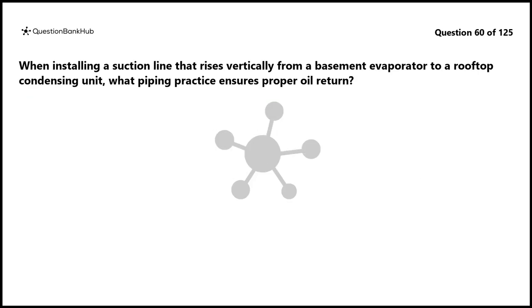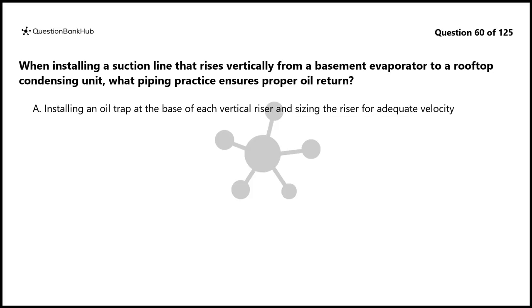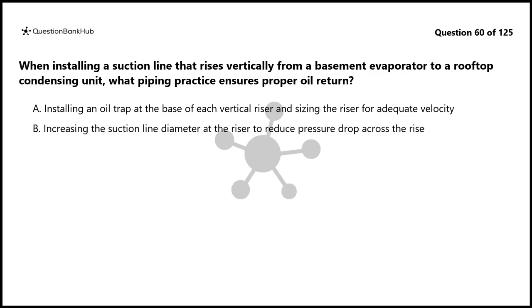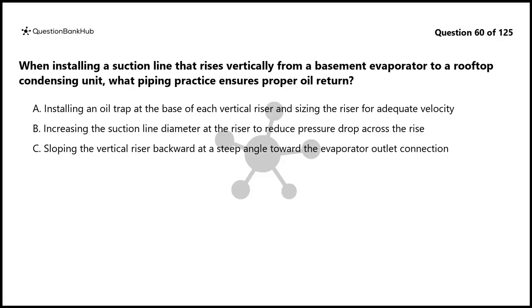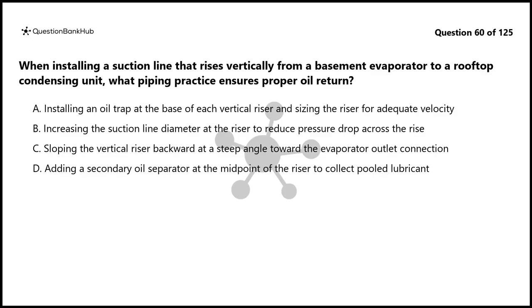Question 60. When installing a suction line that rises vertically from a basement evaporator to a rooftop condensing unit, what piping practice ensures proper oil return? A. Installing an oil trap at the base of each vertical riser and sizing the riser for adequate velocity. B. Increasing the suction line diameter at the riser to reduce pressure drop across the rise. C. Sloping the vertical riser backward at a steep angle toward the evaporator outlet connection. D. Adding a secondary oil separator at the midpoint of the riser to collect pooled lubricant.